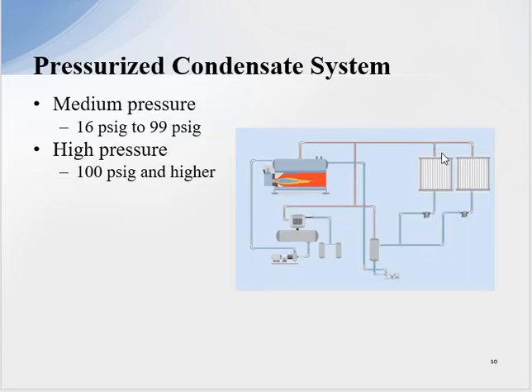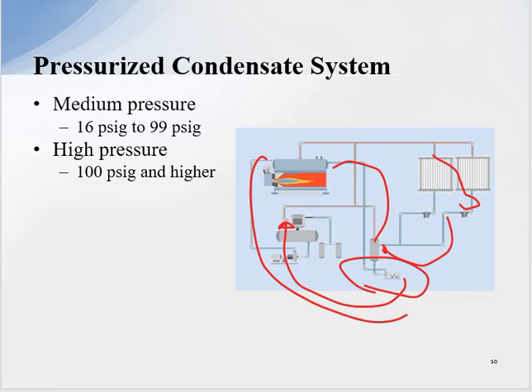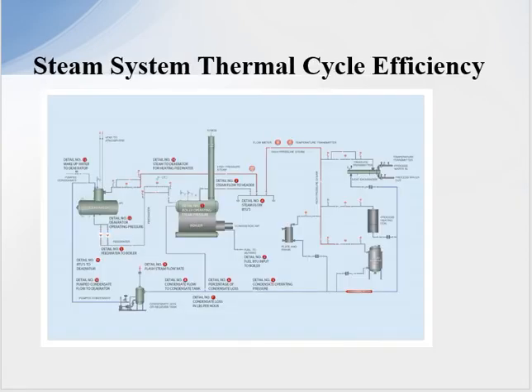In pressurized return systems, because we have high pressure on the process applications and the pressure is great enough, we can go into a pressurized return system and recover the flash steam. Depending on distances from the boiler plant, we might have a tank running at fifty PSI and then pump the condensate back to the deaerator, or possibly pump it directly back into the boiler. The goal with any system is to return the condensate as hot as possible, containing the flash and sensible energy to deliver to areas where we can recover it. This increases steam system thermal cycle efficiency, which is a critical benchmark today.